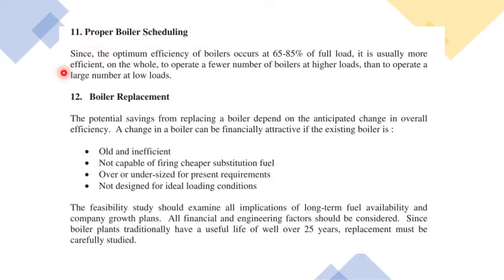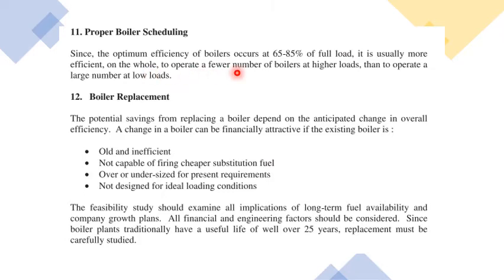The eleventh point is proper boiler scheduling. Since optimum boiler efficiency occurs at 65–85% of full load, it is more efficient to operate fewer boilers at higher load than to operate a large number of boilers at low load. For example, instead of running multiple boilers at 25–35% load each, you should consolidate and run one or two boilers at 65–85% load, keeping the rest on standby.